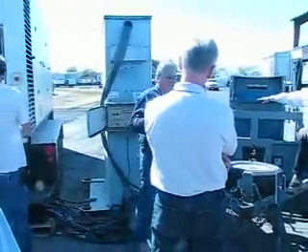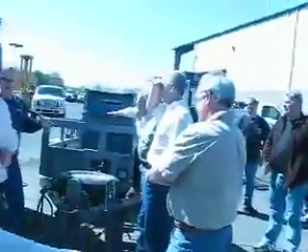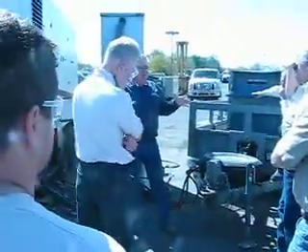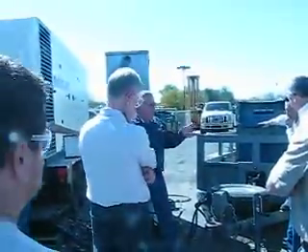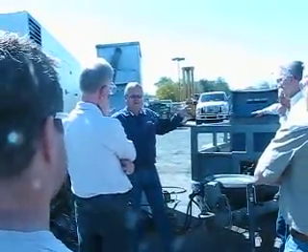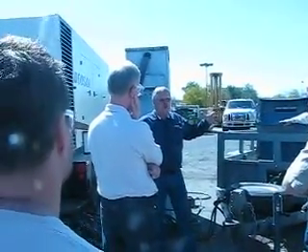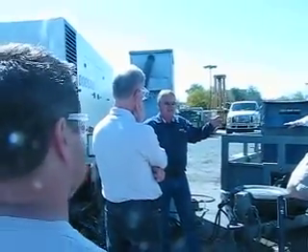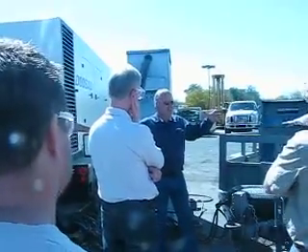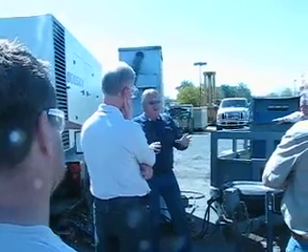We haven't got into paralleling, and we're going to do that here, just days get short. When you're paralleling generators, again, what controls KW? What's KW all about? Work. And who's doing the work? Your building? No. The engine, the prime mover. So KW is all about the prime mover.